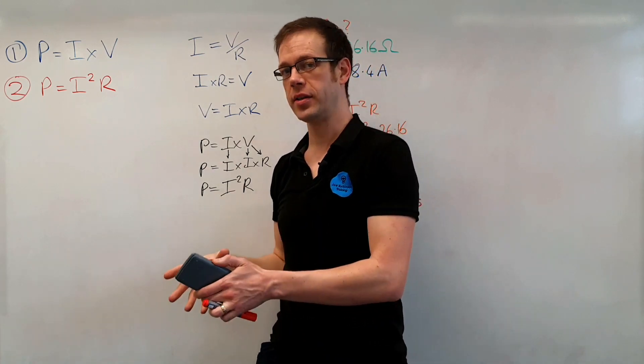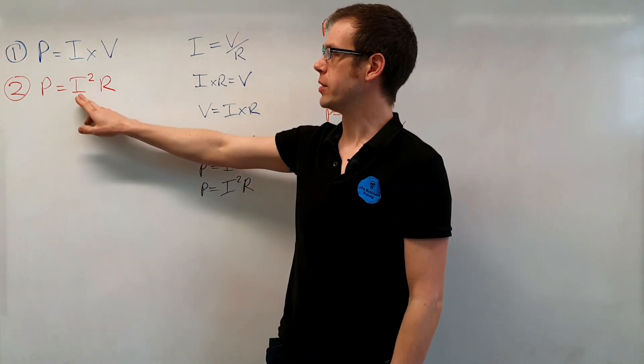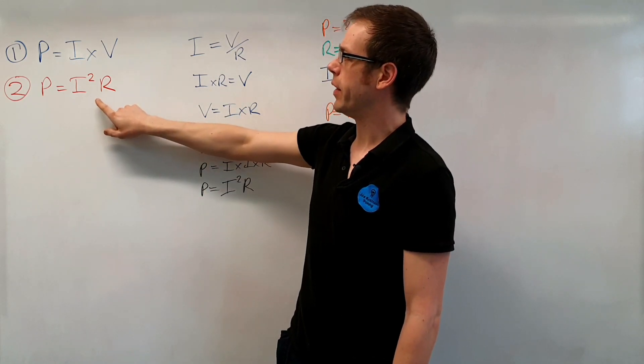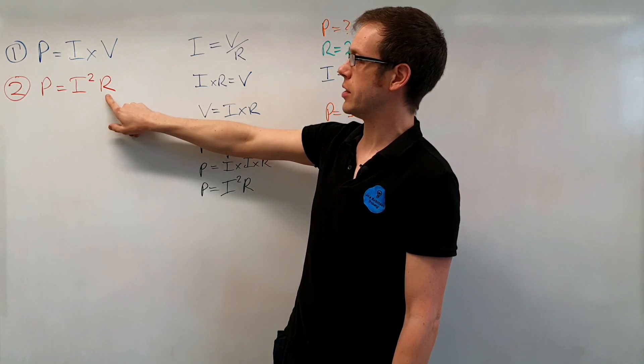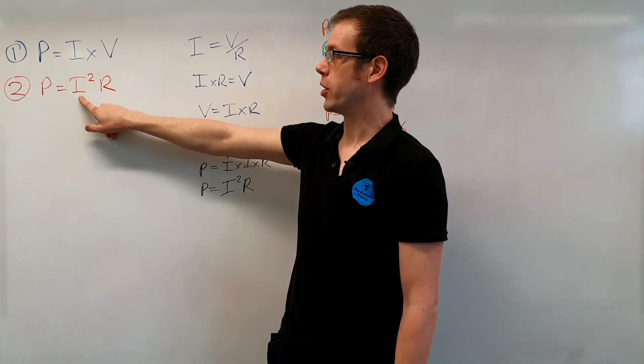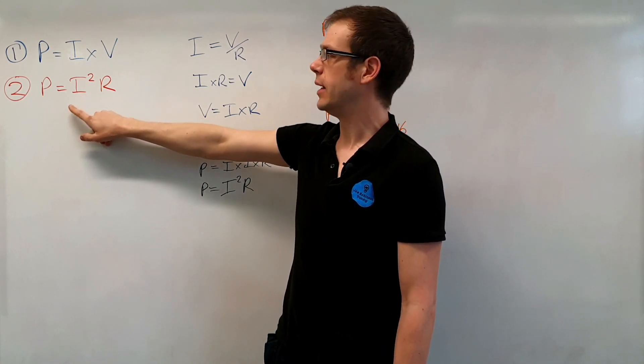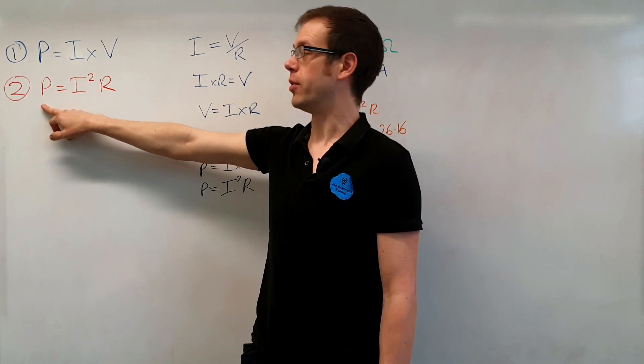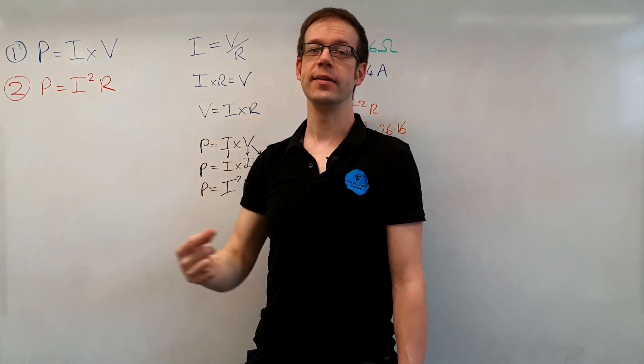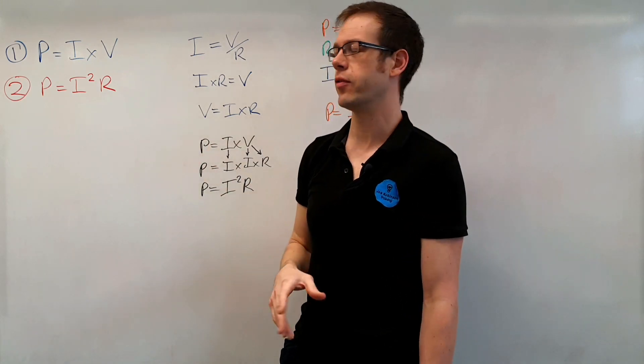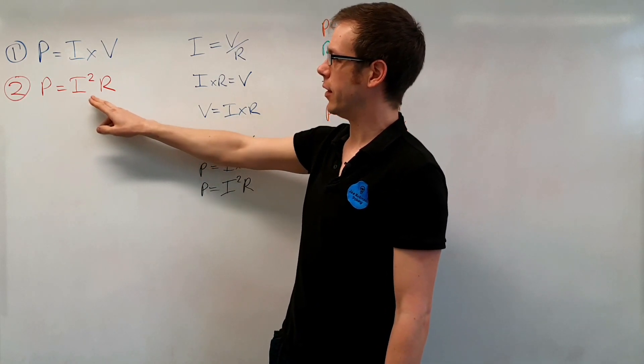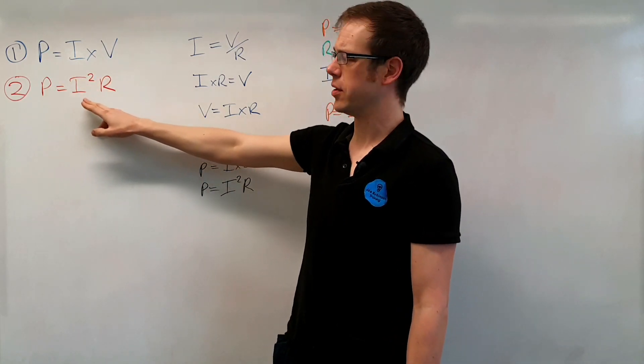Now we know that when you pass current through a transformer when you use a transformer it starts to get hot. Part of the reason for that is you've got current flowing through a resistance the resistance of the winding of the coil there. So if we take the resistance of the coil and times it by the current flowing through the coil squared it will actually tell you how much power is being lost by that transformer in the form of heat due to the copper winding. There are other reasons why transformers get hot and waste energy but this is the one that relies on the resistance of the copper.